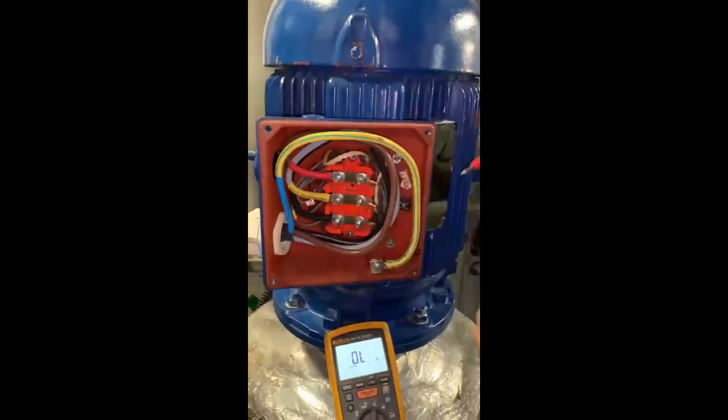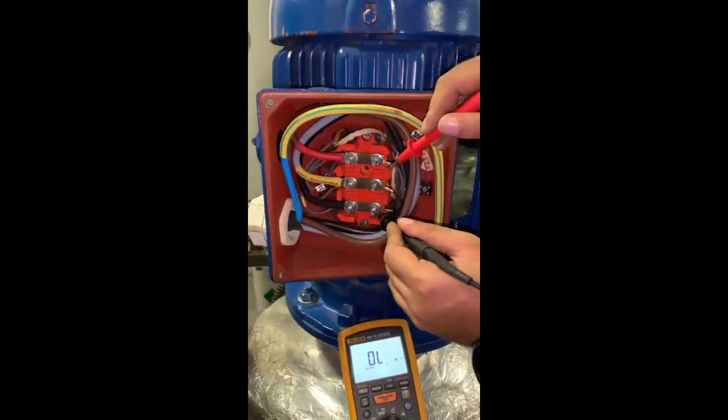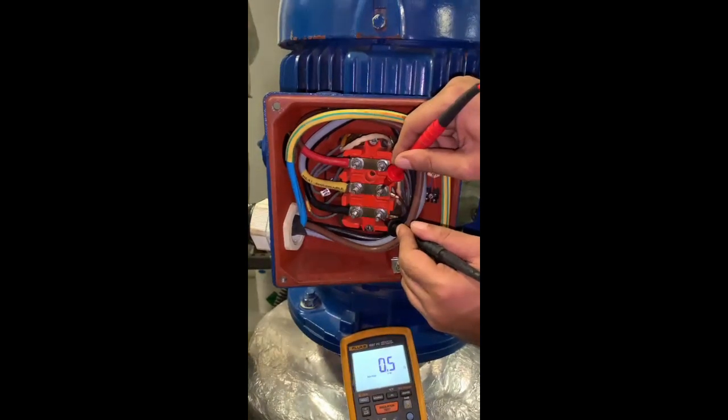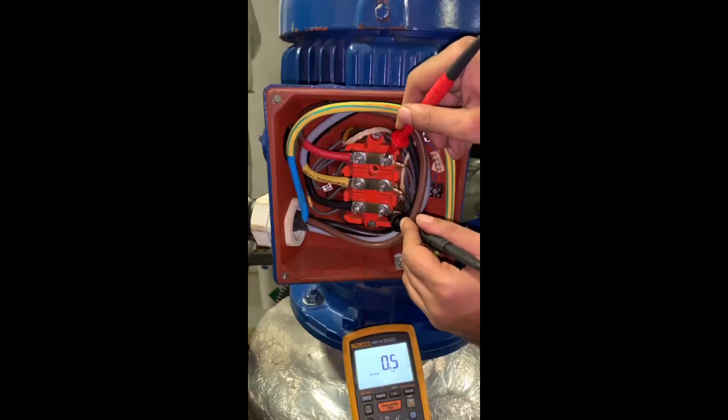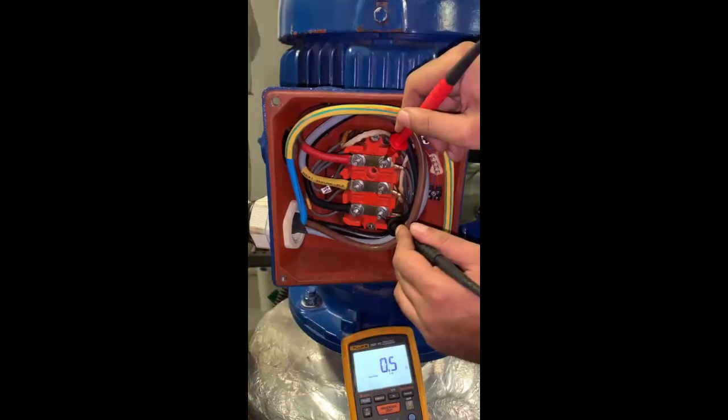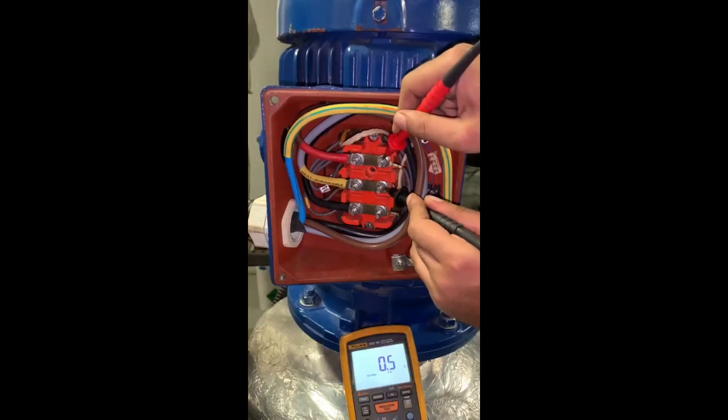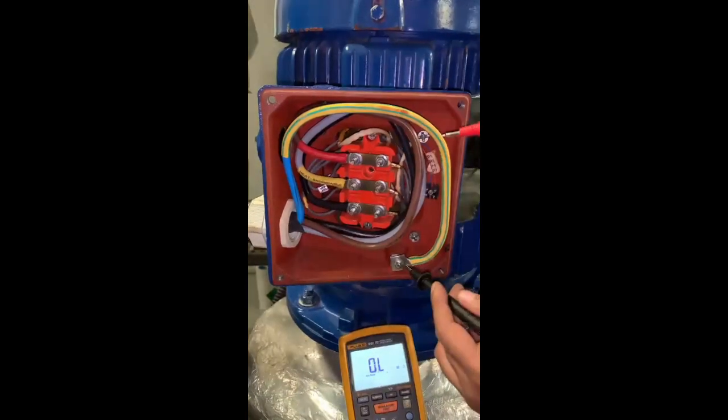As shown in the example, terminal V1 and W1 shows a resistance of 0.5 ohms, terminal U1 and W1 shows a resistance of 0.5 ohms, and terminal U1 and V1 also shows a resistance of 0.5 ohms. This shows good winding health.